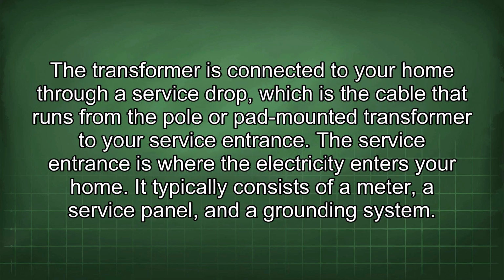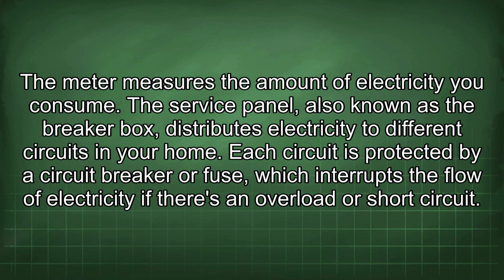The transformer is connected to your home through a service drop, which is the cable that runs from the pole or pad-mounted transformer to your service entrance. The service entrance is where the electricity enters your home. It typically consists of a meter, a service panel, and a grounding system. The meter measures the amount of electricity you consume.